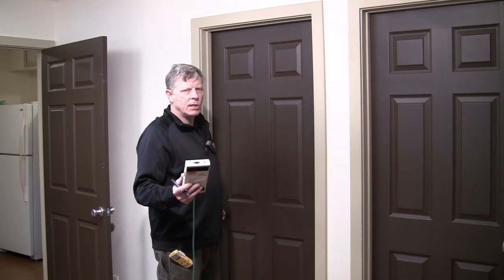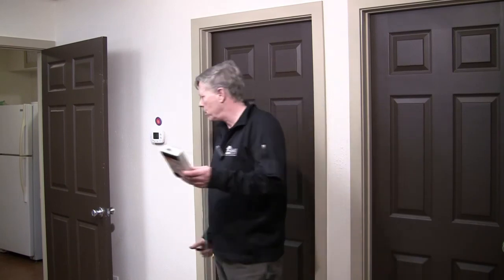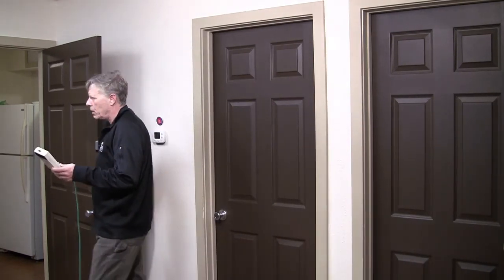Very little change, it's negative 7.6, so we must have a good undercut under that door. Now we can be checking this with a smoke pencil also, but I have a manometer in my hand and the house is small enough I can get that done without the smoke pencil.